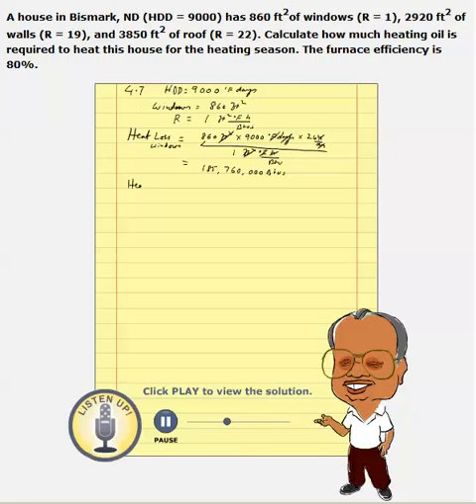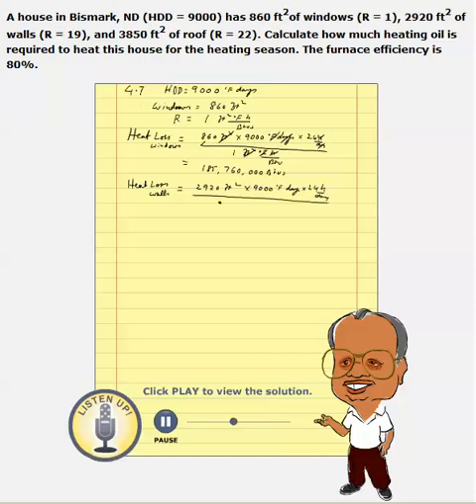Similarly, we can calculate heat loss through the walls. Wall area is 2,920 square feet, times 9,000 degree-Fahrenheit days, times 24 hours per day, divided by the R-value of 19 for walls. Canceling out the units, this turns out to be 33,195,789 BTUs.